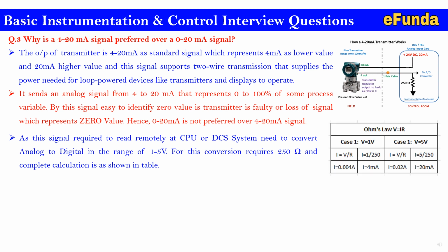Refer to the table, where Ohm's law says V equals IR. We know the voltage and the resistance, and we need to calculate the value of I. In the first case, the voltage level is 1 volt, so I equals V by R, that is 1 by 250 ohm, and the calculation comes to 4 milliamps. Similarly, in case 2, where the voltage level is 5 volt, I equals V by R, so 5 divided by 250 ohm gives a current of 20 milliamp. This is how the 4 to 20 milliamp signal is preferred over the 0 to 20 milliamp signal, and how the current is carried from the field to the control room without dropping of any current.